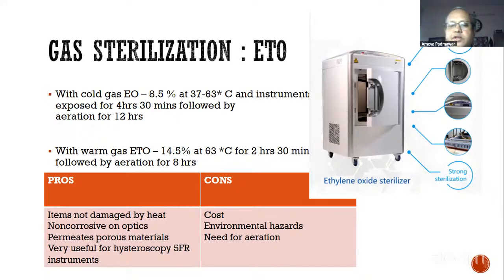So it uses a lower temperature, something like 37 to 63 degrees Celsius, is all that is required. So instruments which are heat sensitive, such as, of course, I do not recommend the reuse of harmonic probes or single use instruments, but to make them more cost effective, you have to appropriately sterilize them, and ETO is a great modality for doing in-house sterilization of these instruments. So it uses ethylene oxide gas, which is 8.5%.